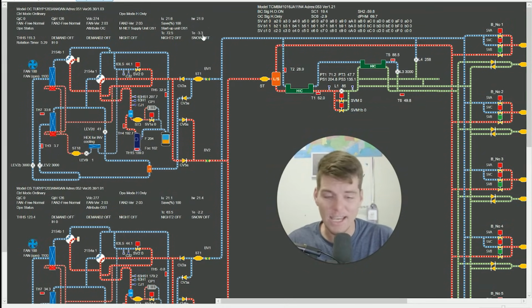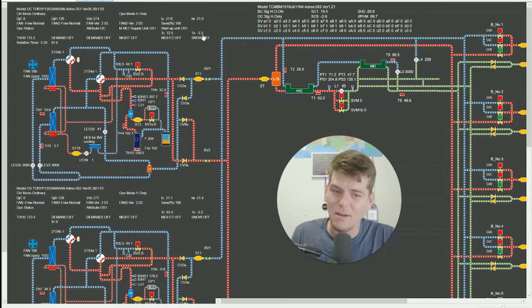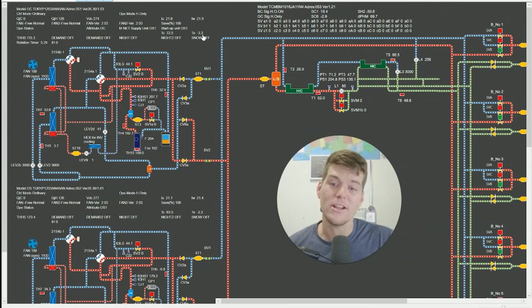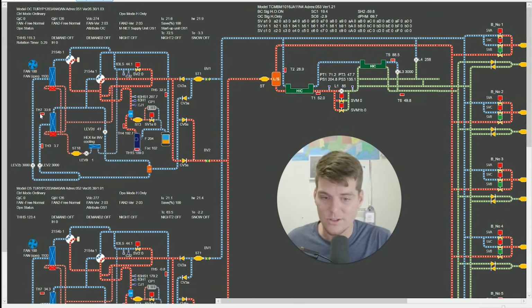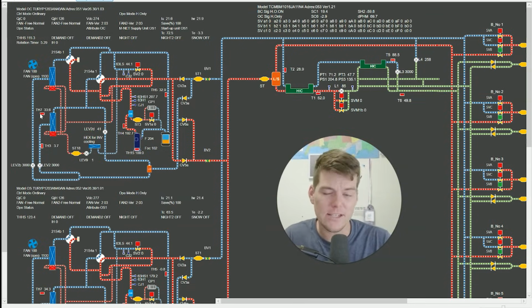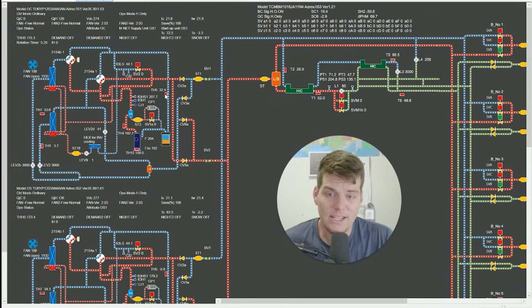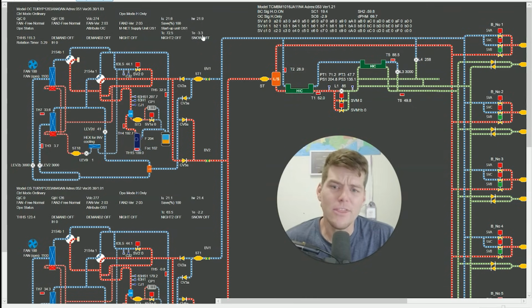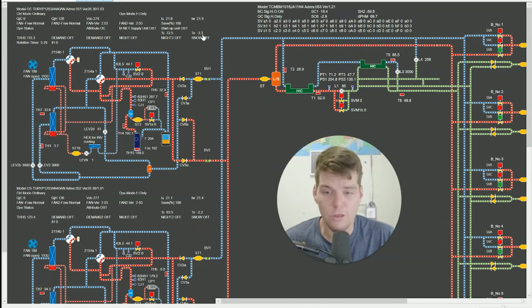Well, if we go to this module here, 32.9, TE is negative 3.2, which isn't uncommon. Negative Fahrenheit just means the pressure is very low and it's probably cold outside or heating. And here on TH7, we can see that it's 33.6. So it's not freezing, but it's pretty close. So with that, 32.9 degrees here, close to ambient, which is a little concerning if this is an evaporator. And that means that we're clearly over 30 degrees suction superheat. So it's starved for refrigerant, right?